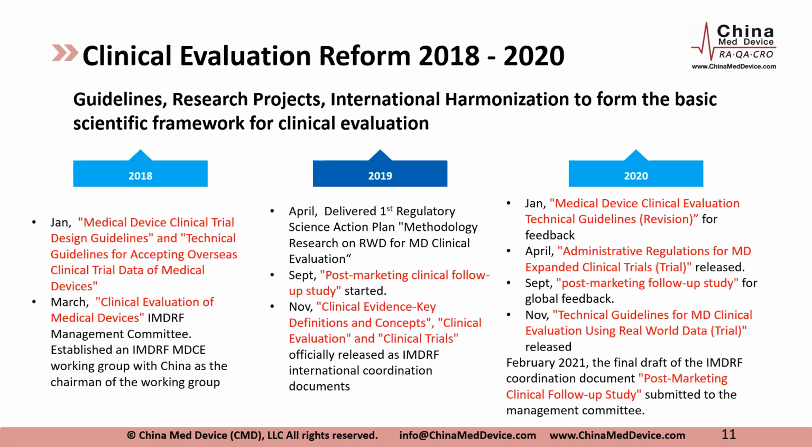And then with the IMDRF, there were 3 documents released in the 2018-19 timeframe. I think it's 2019. They have more definition of what it means for clinical evaluation, what the definition is, and how you prove the evidence. All these concepts were released in November 2019. These are in English.